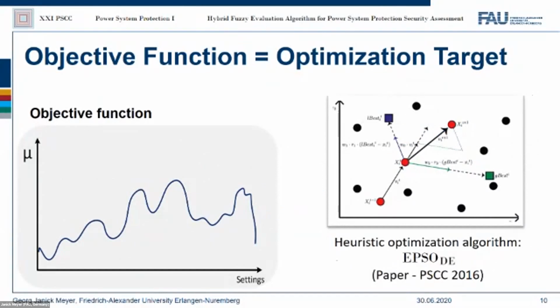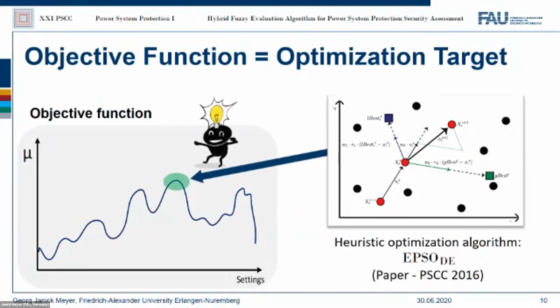Proven to be efficient, we used an EPSO-DE particle swarm algorithm, which was first introduced in 2016 at the PSCC in Genova. It is a hybrid heuristic optimization algorithm combining the advantages of evolutionary algorithms, differential evolution, and particle swarm optimization. The algorithm optimizes all fuzzy sets of all settings of all relays simultaneously. We applied the hybrid fuzzy evaluation and optimization on an adapted version of the IEEE 9 bus grid to find the best possible setup.